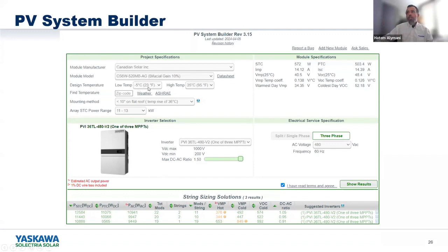After that, you'll just put the temperature limitation of your installation area. These are very important because based on this temperature, the voltages and the current information are going to be adjusted per NEC code, and that will let us know how many modules we can put on the string. So these two values are very, very important. And then basically you can select the mounting method. This is also going to add a little bit of changes on the voltages of the modules. If it's on top of the roof, then there's going to be an additional factor that we have to add for the temperature based on the NEC requirement.